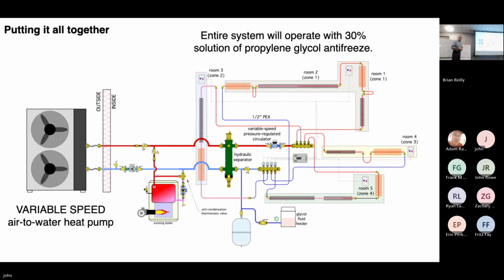Do you ever see a situation where, sometimes obviously the systems can provide domestic hot water, but say the domestic hot water is a really high load, and you don't want to tax the system with that? Say there's a zone that goes to a freestanding water heater, maybe a heat pump water heater or a fuel-source one, that gets essentially a heating zone of its own, where you're putting in a bit warmer water to it, rather than trying to pull it up to 120, 140. Sure. And sort of reduce the energy cost of that, since the system's already running.